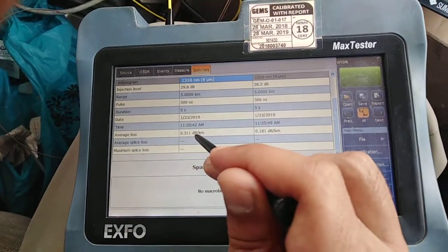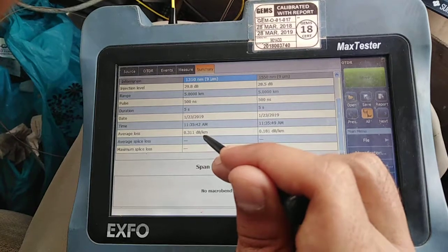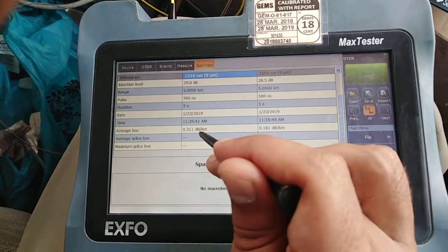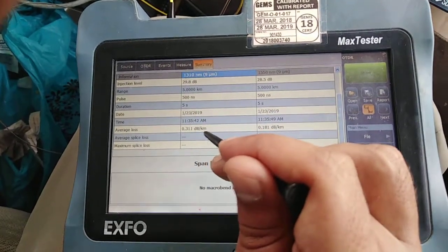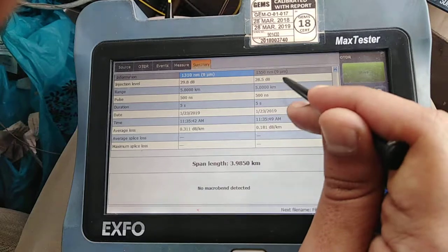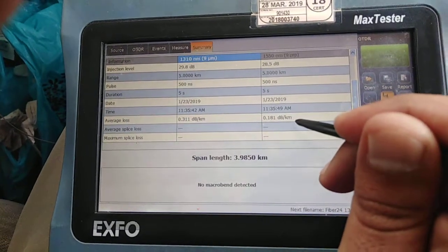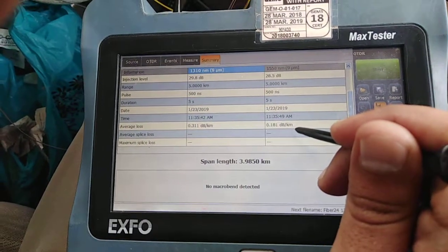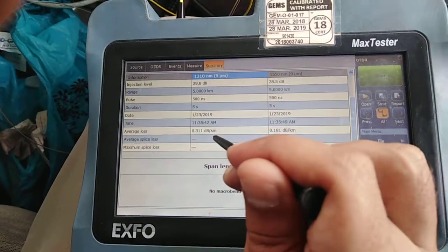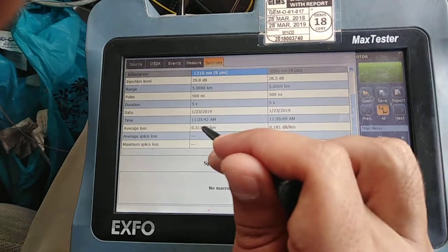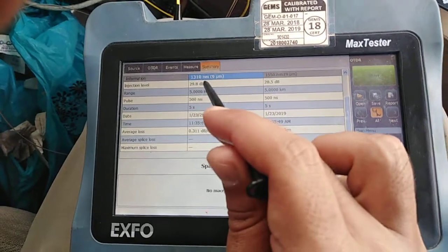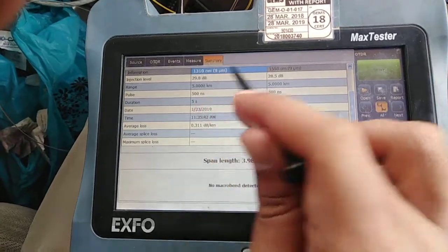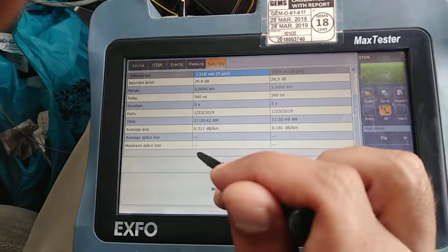The average loss at 1310 is 0.311 dB per kilometer, and at 1550 it is 0.181 dB per kilometer. In my other videos I will show you how to calculate the acceptable loss at 1310 and 1550 nanometers.